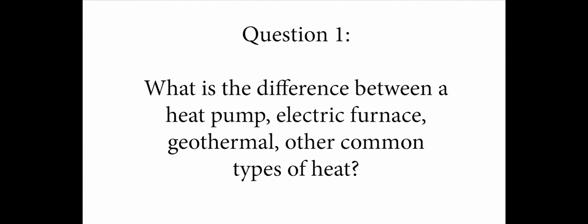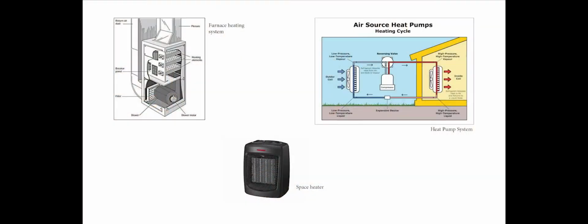What's the difference between a heat pump, electric furnace, geothermal, and other common types of heat in a home? So there are several common forms of electric heating. Electric furnaces, baseboard heaters, ceiling cable heat, and small space heaters are all similar in the way that they operate. They're all resistive electric heating solutions. Those are all, say, less efficient than an air source heat pump, which is less efficient than a geothermal system. An air source heat pump actually extracts heat from the outside air, whereas a geothermal system extracts heat from the ground and the earth itself.